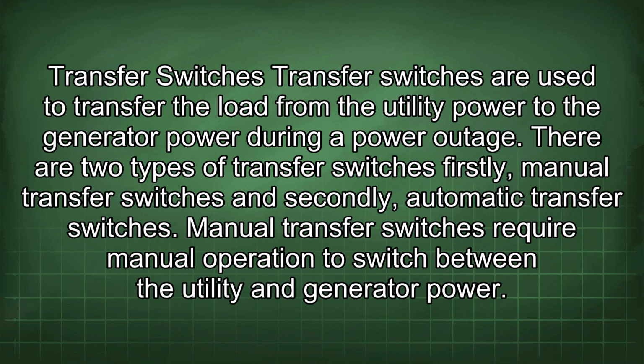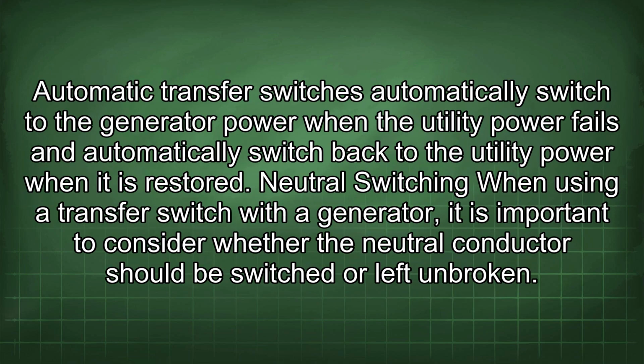Transfer switches. Transfer switches are used to transfer the load from the utility power to the generator power during a power outage. There are 2 types of transfer switches. Firstly, manual transfer switches, and secondly, automatic transfer switches. Manual transfer switches require manual operation to switch between the utility and generator power. Automatic transfer switches automatically switch to the generator power when the utility power fails and automatically switch back to the utility power when it is restored.